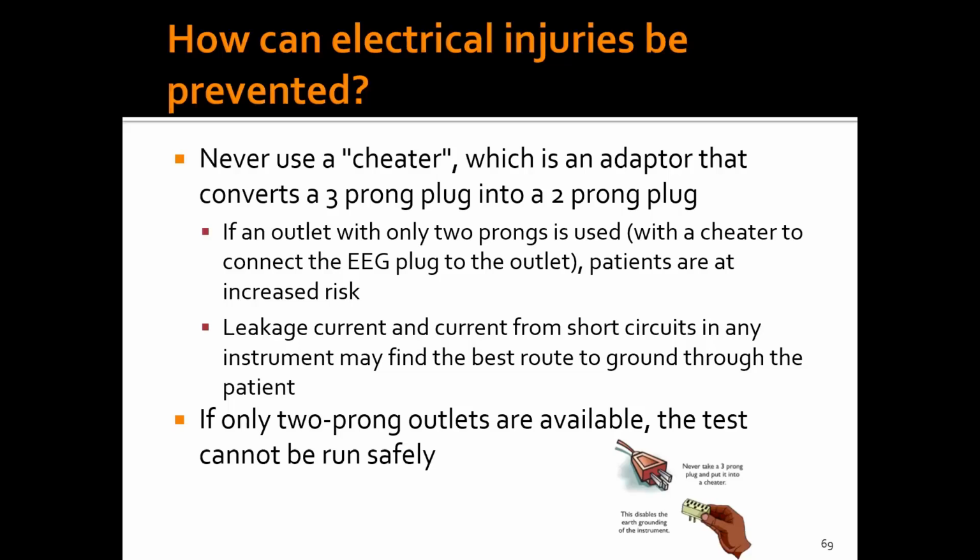If only 2-prong outlets are available, then you can't run the test safely. You cancel it. Nothing is more important than keeping our patients safe. And if we can't run the test safely, we're not doing it.